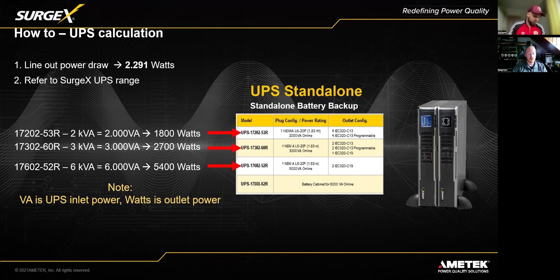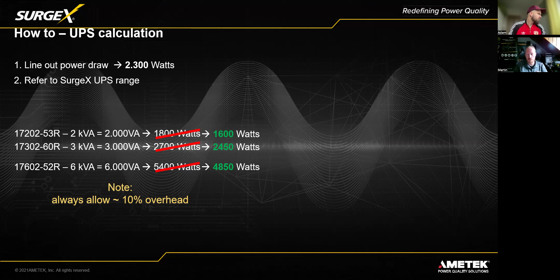So that's why we always allow 10% overhead to cover bad power conditions, giving us 1600 watts, 2450, and 4850 watts to be safe. Again, it's the same conversation as with the PDUs: you're better off using a slightly bigger device to power everything at a lower volume level than using a very small one running at 100%.